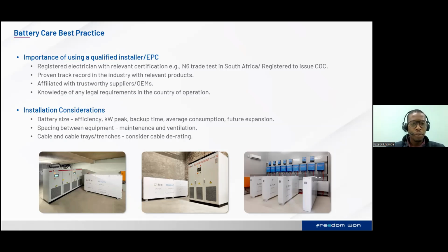So it's very important for installers and EPCs to be acquainted with the legal requirements. For instance, in South Africa, there are certain legal requirements which are put in place that the BESS systems must adhere to. Take into consideration the NRS 097-2-1, which looks into small scale embedded generation systems. There's the BESF as well, which caters for grid connection code for battery energy storage facilities. So we need to be familiar with these legal requirements in order to be able to integrate our systems with the already existing, either the transmission system or the distribution system.